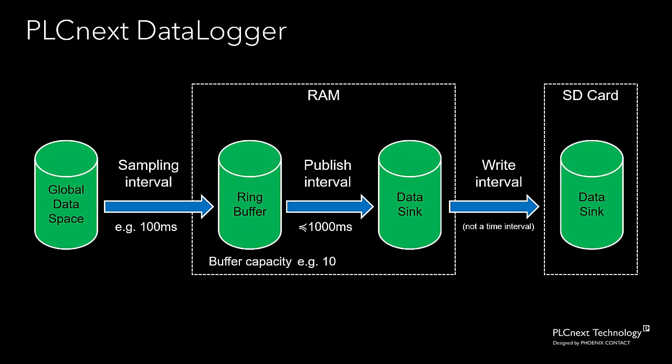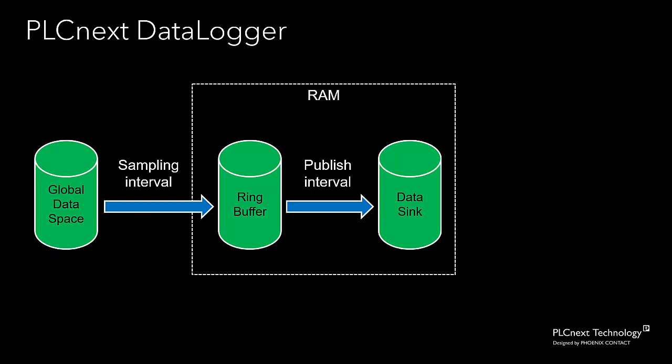The data logger described here is called a database type data logger, where the data ends up in a data sink on the SD card in persistent memory. There's a second type called a volatile data logger. In that case, we simply omit the final step and data just ends up in the in-memory data sink in RAM. We can retrieve data from that in-memory data sink using an RSC service in the PLCnext runtime. Of course, when the PLCnext runtime shuts down or the PLC reboots, that data will be lost.